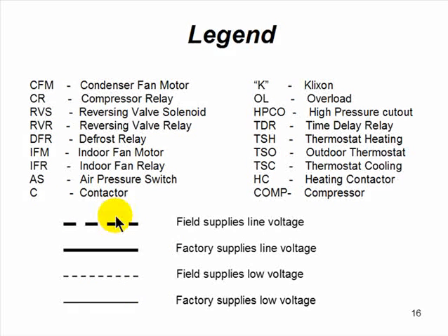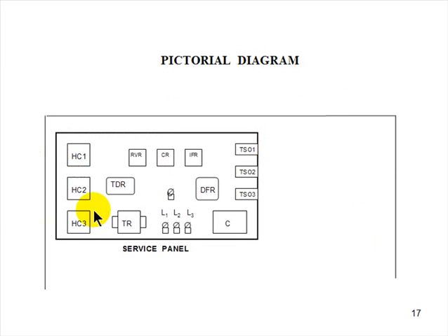And this is very common, and unfortunately there are no rules on low voltage and how it should be represented or what the symbol should mean. It's chaos, so you will see deviation from that. Very often dashed lines mean that something is ganged, that when you throw the system switch into cooling, you automatically put Y and G common. That kind of thing. That's the schematic, and that was the legend.